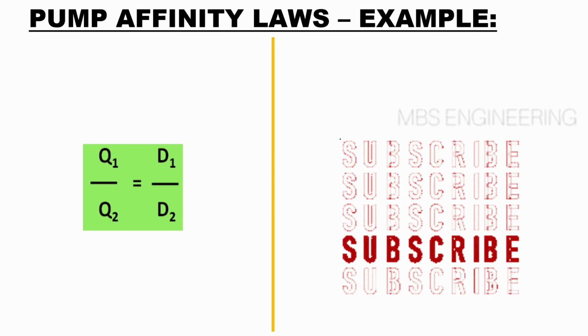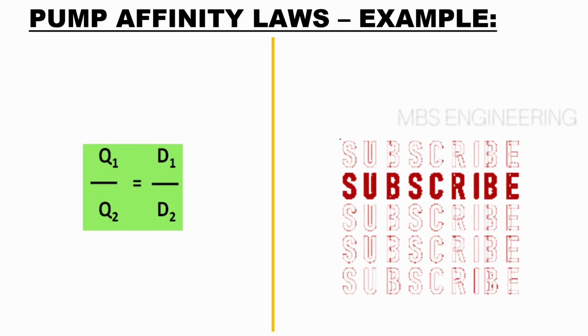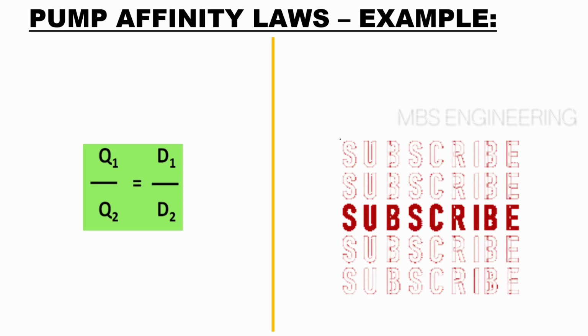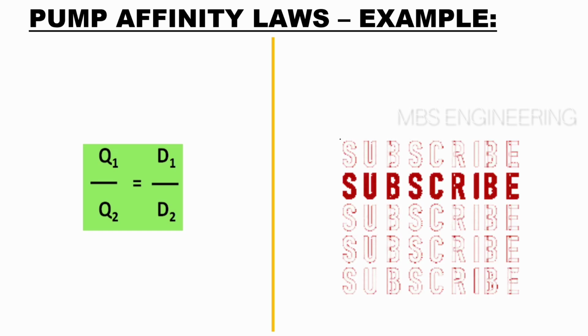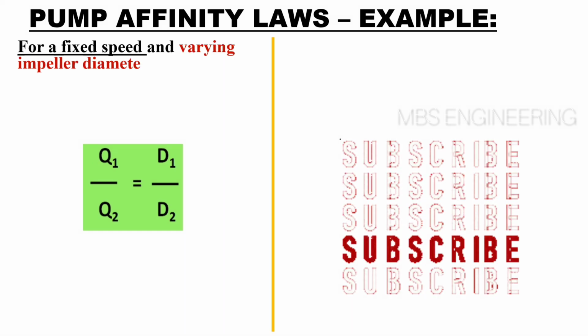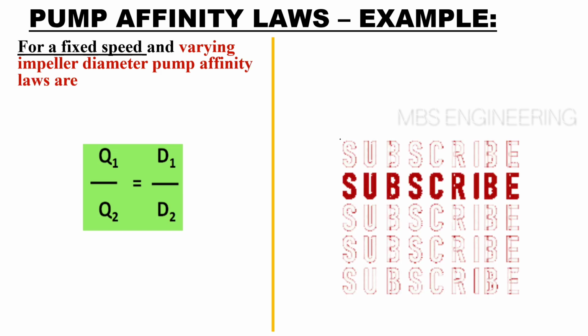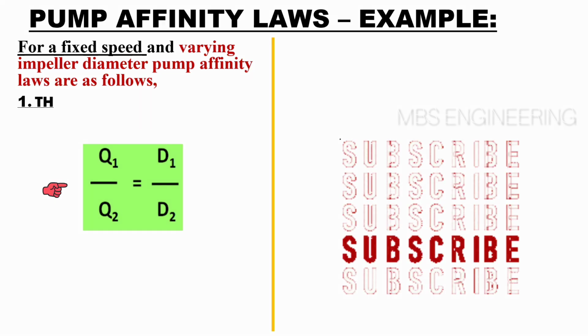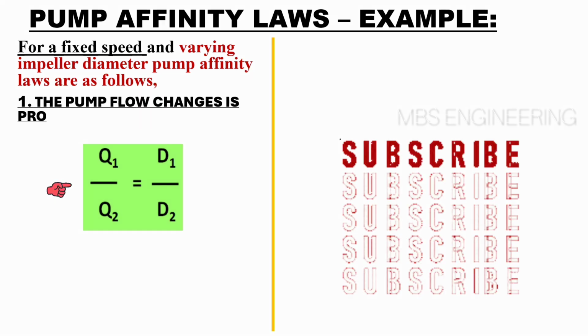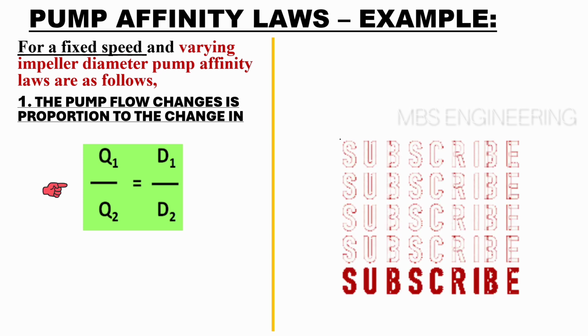Next, we will learn about the formula for pump affinity laws and will understand with sample calculations. Next, we will learn about the first formula for pump affinity laws. For a fixed speed and varying impeller diameter, pump affinity laws are as follows. The first affinity law: the pump flow changes in proportion to the change in impeller diameter.